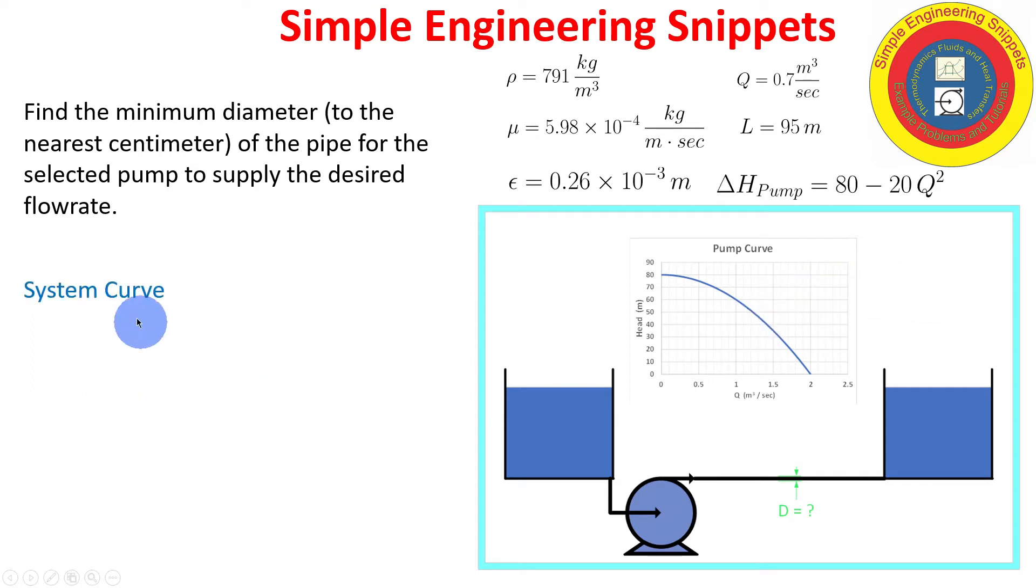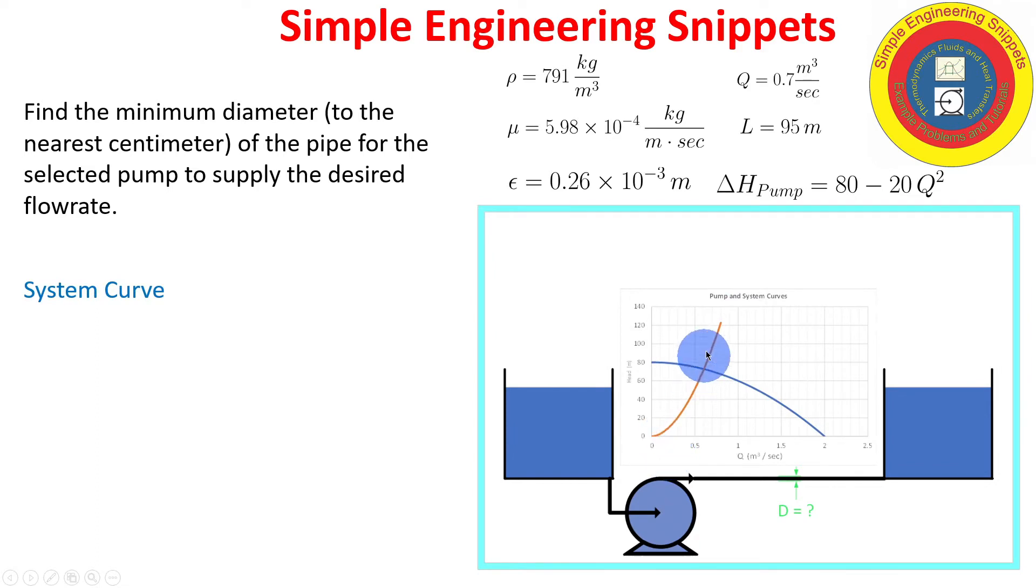So that'll be key as we iterate to find the correct diameter for this problem. But we have the pump curve. But let's look at a system curve. So here's an example in gold, the system curve. And as you might recall, the solution is where these two curves intersect, denoted here with a red circle.